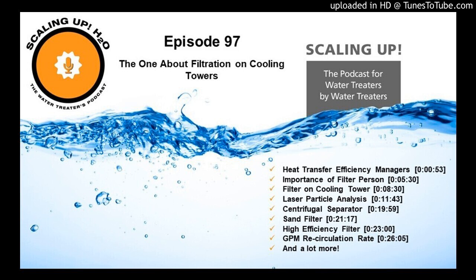Now, I've seen the use of sweeper jets around the cooling tower basin to try to keep things stirred up. Can you speak a little around that? Sure. It's opinion, I guess. In my mind, the design of a cooling tower sump, the reason why there's this big sump there that's maybe 12 inches deep or whatever, the reason why that sump is there is because when you bring a lot of particulate into a cooling tower from the air, the bigger stuff, you don't want it to go into the system. You want it to settle in the sump.